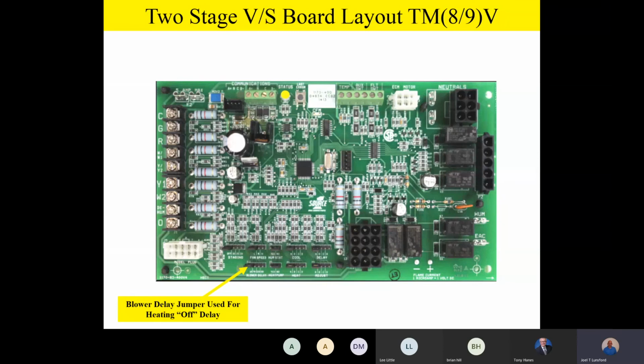The final jumper we're going to talk about is our staging jumper. Now, unlike our previous boards that we talked about, the staging on this particular board, the variable speed board, does not have the auto function. It doesn't have that intelligence built in on the board. We just didn't have enough room electronically on the board to do that. But we still give you a 10, 15, or 20-minute selection if you have a single stage thermostat.